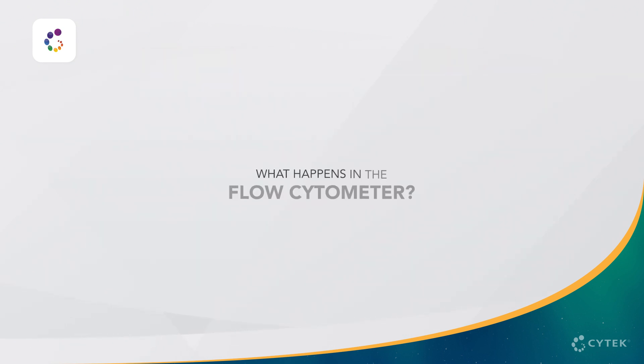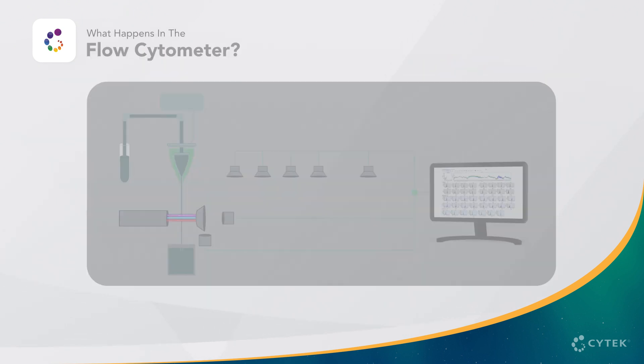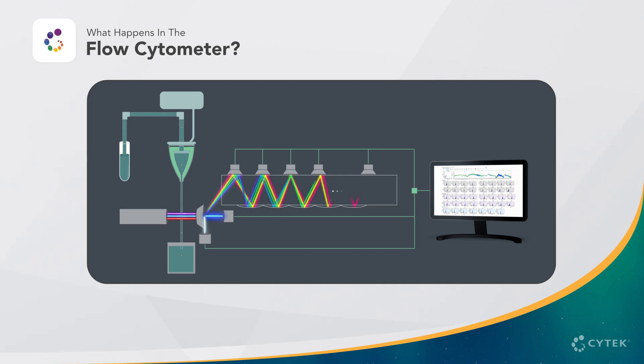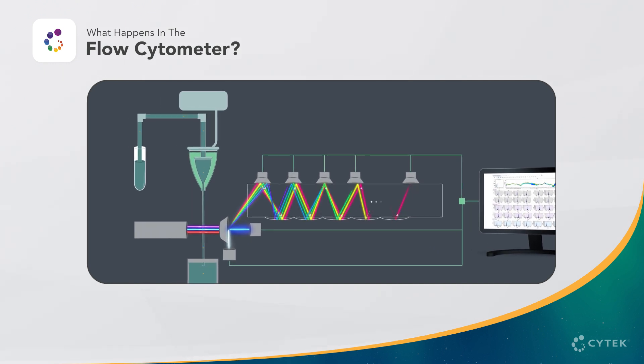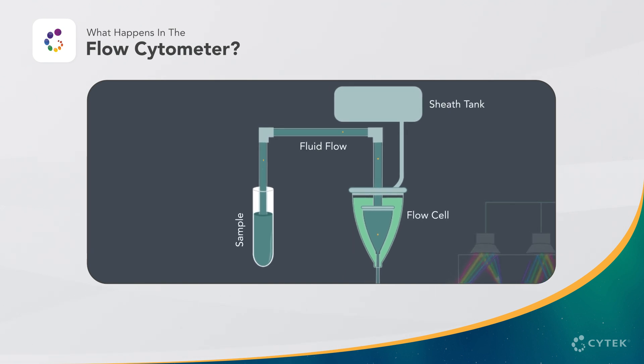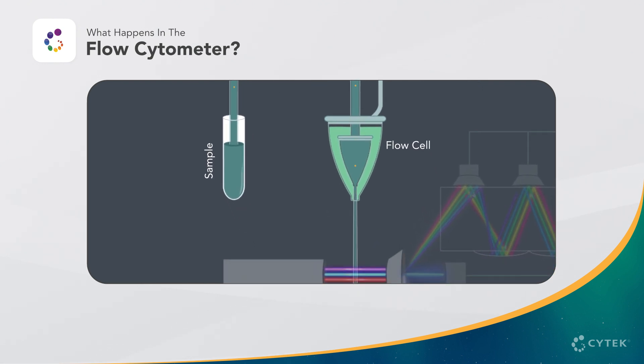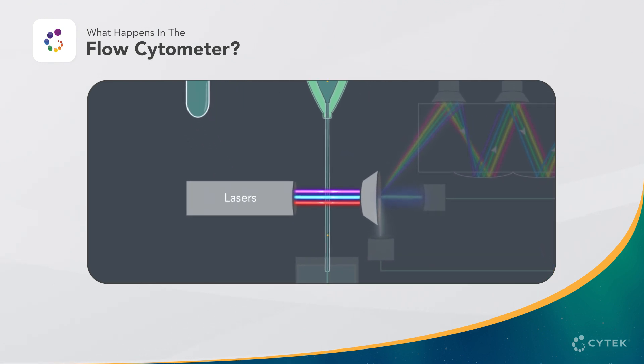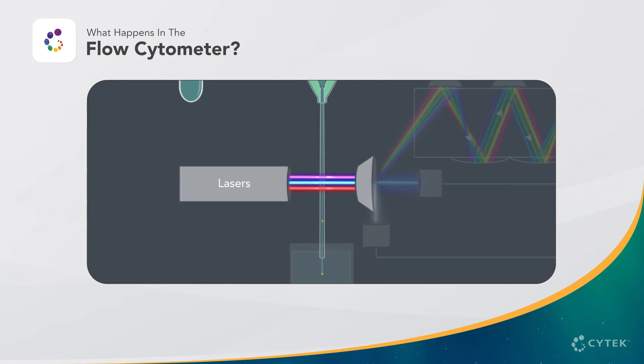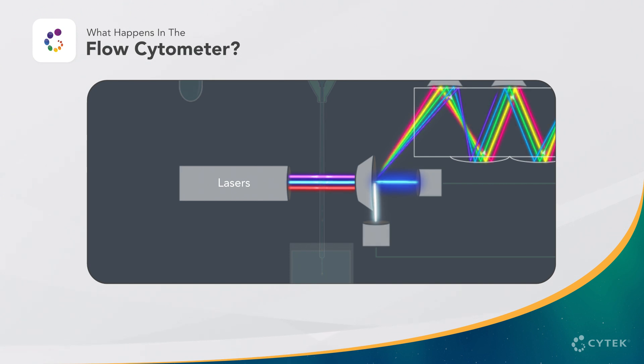What happens in the flow cytometer? Let's trace the path of cells through the various components of the flow cytometer. First, the sample is taken up by the cytometer and enters the fluidic system. The cells are aligned single file in the flow cell, then pass through each of the lasers at the interrogation point. As each cell is interrogated, photons of light are collected from a few sources.